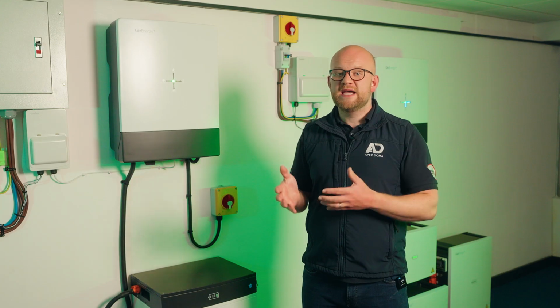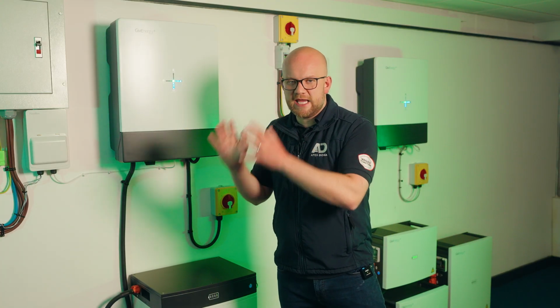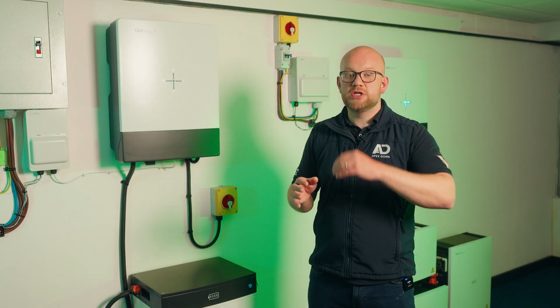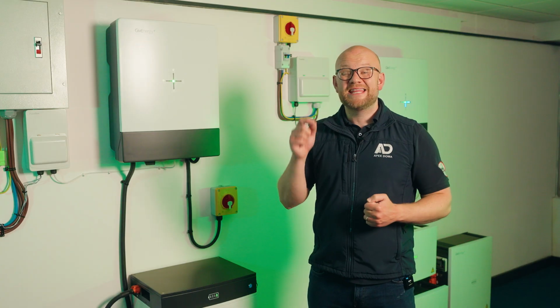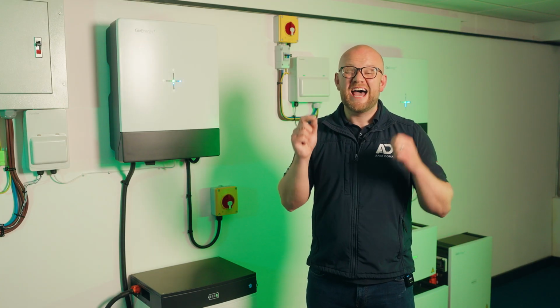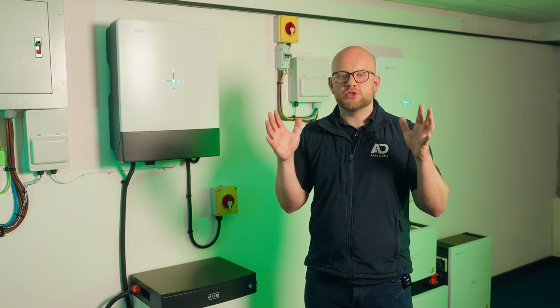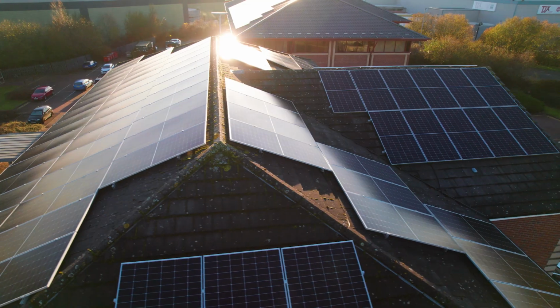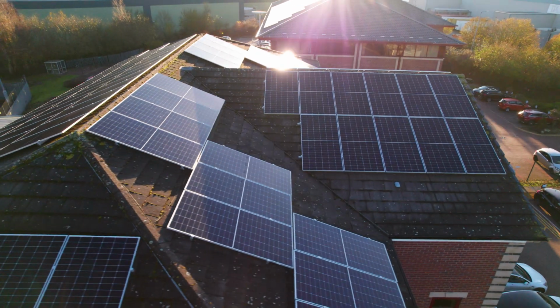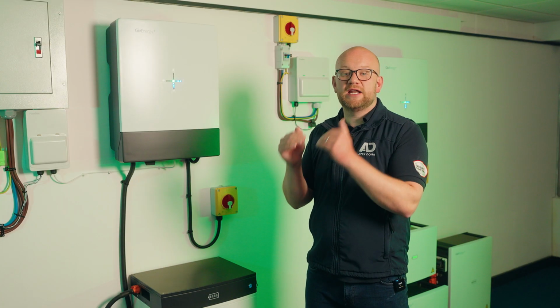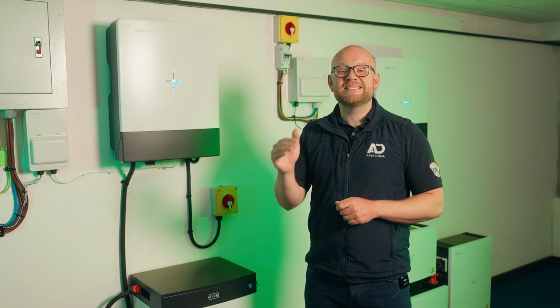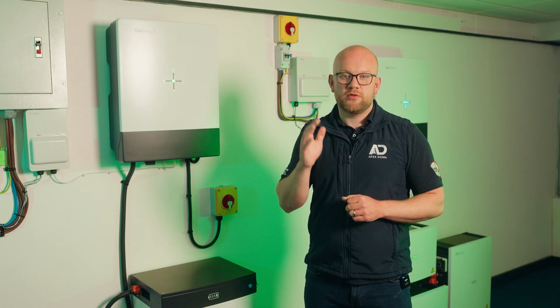But for those with a bigger roof, where the low voltage GivEnergy range can't process enough of that solar generation, this is where the high voltage hybrid inverter comes in. So in the single phase, as I've mentioned, we have an 8 kilowatt and a 10 kilowatt option. They have a maximum amount of input of solar of 15 kilowatts, so 15,000 watts worth of input. This is done over 2 maximum power point trackers, but you can have up to 4 inputs. So if you've got really big arrays on a roof, this will be able to cope just fine. In the 3-phase options, we have an 11 and a 20 kilowatt inverter, and they can take up to 30 kilowatts worth of solar.